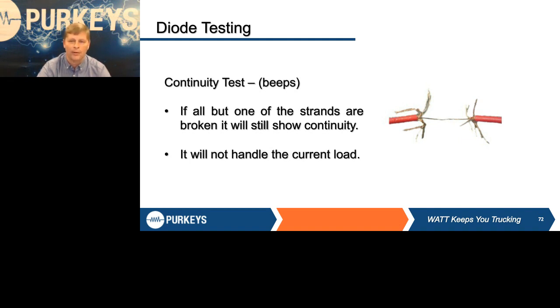Can that wire handle any current? No. Same thing if I take that same piece of wire, and instead of cutting it, I stab it once with a test light and let it sit on the bottom of the trailer for a year, getting full of green gunk and corrosion - what's the end result? It's got about the same capacity as that broken wire. So whether it's broken, like in this picture, or severely corroded, it will still show continuity, but it does not have the ability to handle any current.